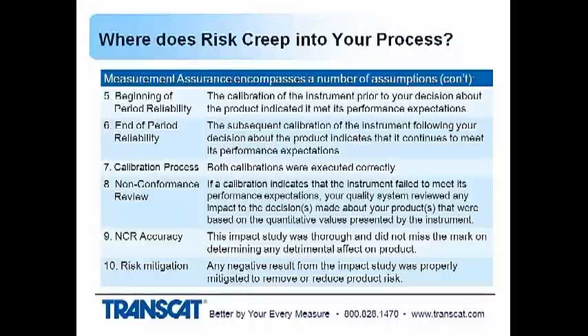And then the end of period reliability is at the end of the calibration cycle, that subsequent calibration, and does it indicate that there was any error in the instrument when you were using it to make decisions about the process? And then the calibration process itself. Were those calibrations executed correctly? And I'll go into more detail of that in a few minutes.